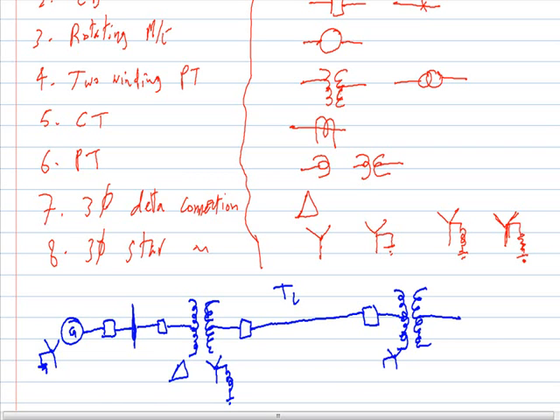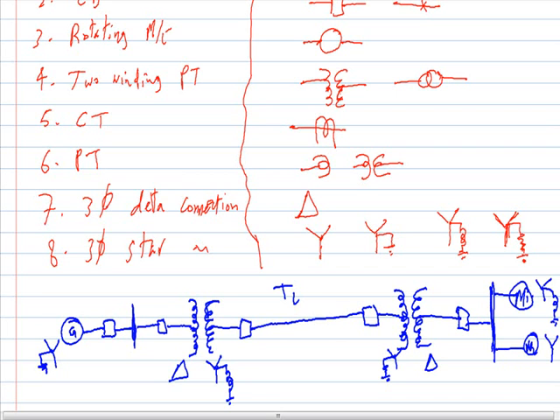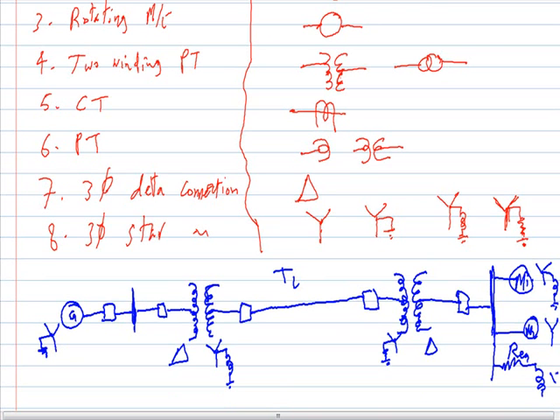Then we have a step-down transformer with the star winding grounded through a resistance and a delta winding on the other side, followed by another circuit breaker, then another bus bar. On the bus bar we have electric motor 1 and electric motor 2. Motor 1 is grounded through a reactor and motor 2 has an ungrounded neutral. Then we have an electric load represented by an equivalent resistance R and equivalent reactance XL. This is the typical power system one-line diagram.